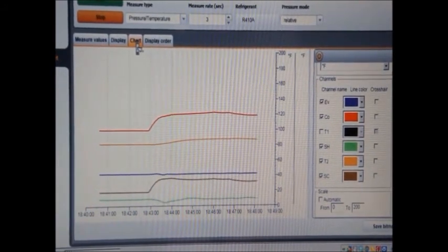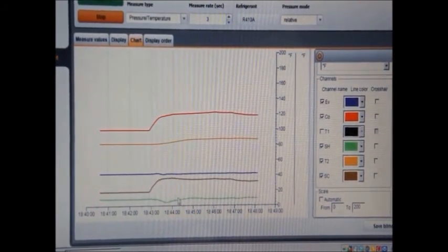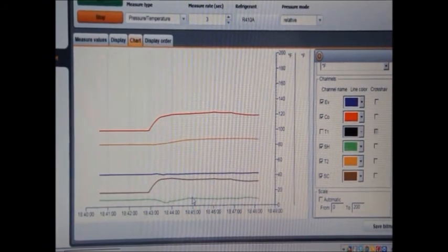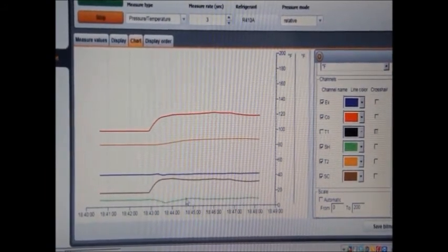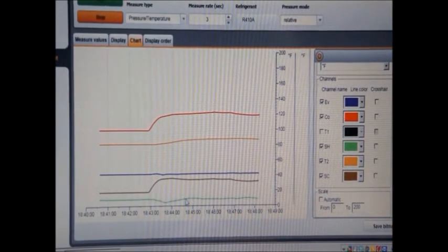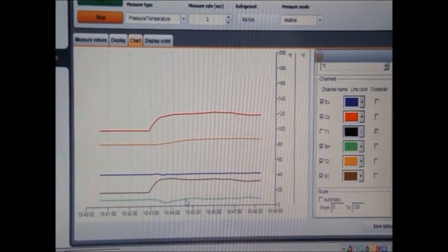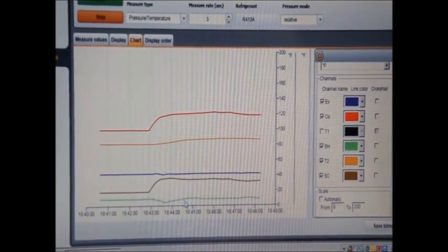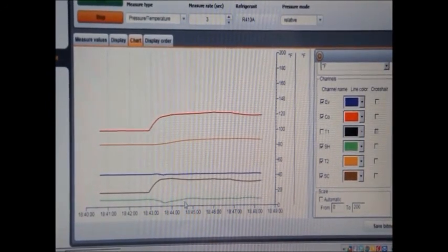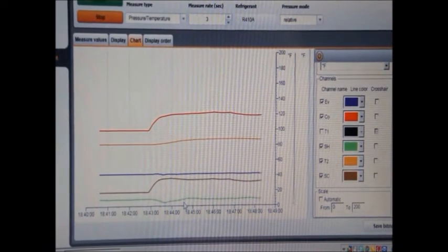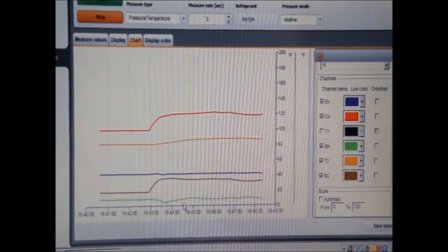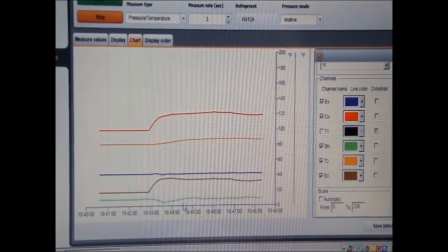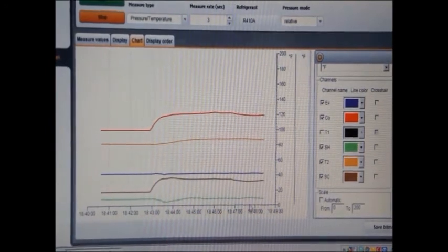You can see our superheat's really sort of a nice flat line across the bottom here. This is a 16 SEER unit and it's the first time I really looked at it like this and it sort of caught me off guard. It's not a normal characteristic I've seen before with these types of units. So just something new.